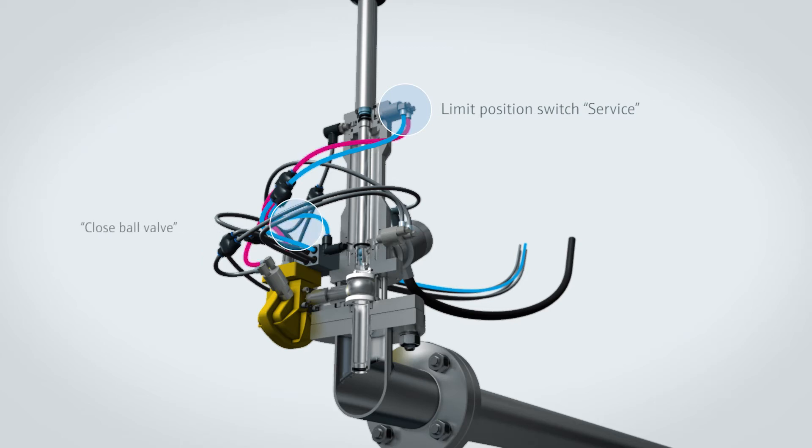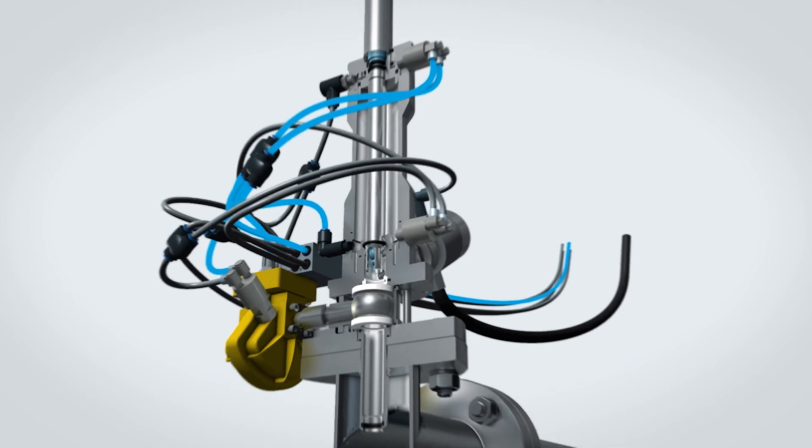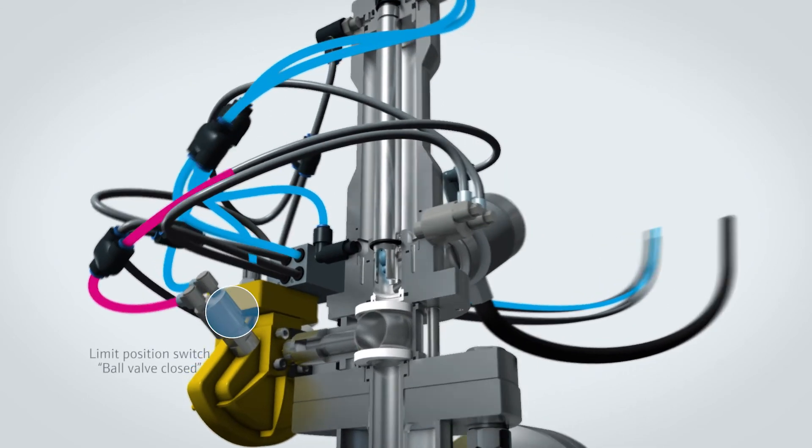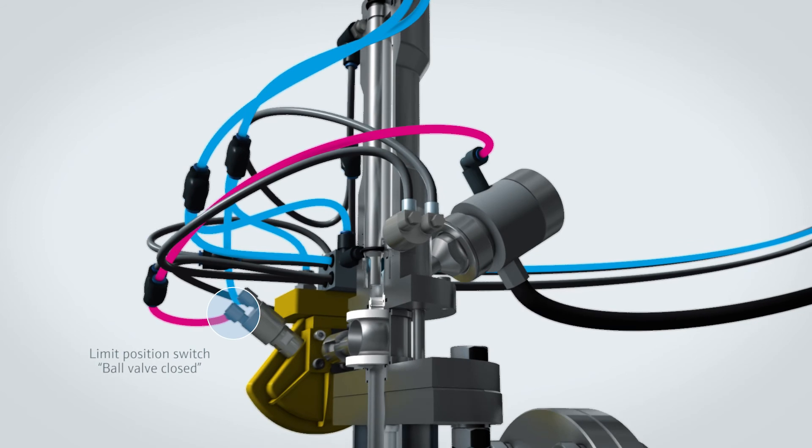This causes air pressure to be applied to the close ball valve inlet and the ball valve closed pneumatic limit position switch. When the ball valve is completely closed, the ball valve closed pneumatic limit position switch conveys the compressed air onwards, causing the optionally installed automatic outlet safety seal to open.